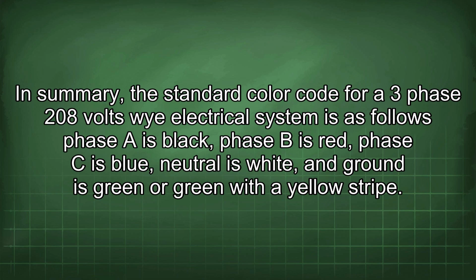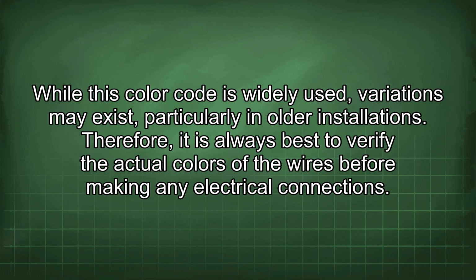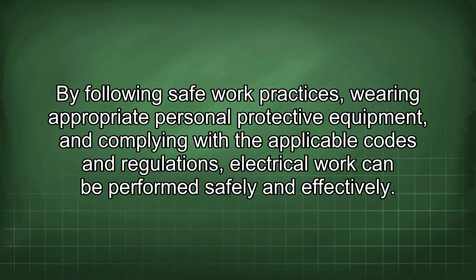In summary, the standard color code for a 3-phase 208-volt Y electrical system is as follows: phase A is black, phase B is red, phase C is blue, neutral is white, and ground is green or green with a yellow stripe. While this color code is widely used, variations may exist, particularly in older installations. Therefore, it is always best to verify the actual colors of the wires before making any electrical connections. By following safe work practices, wearing appropriate personal protective equipment, and complying with the applicable codes and regulations, electrical work can be performed safely and effectively.